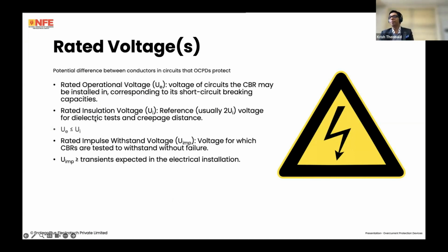You've also got the rated impulse withstand voltage. These are the voltages which circuit breakers are tested to withstand without failure. This relates to surge currents and transients in the electrical installation. I won't go into too much detail about this, but basically it has to be rated to a value greater than the transients expected in the electrical installation. There are also specific requirements for this in IS 732 and NEC.